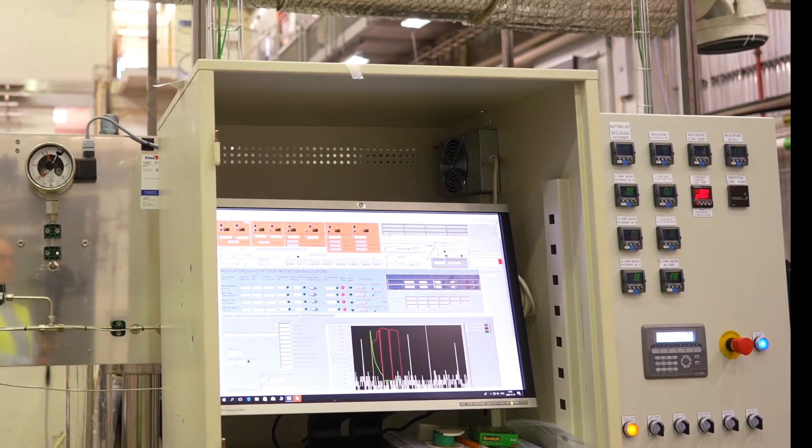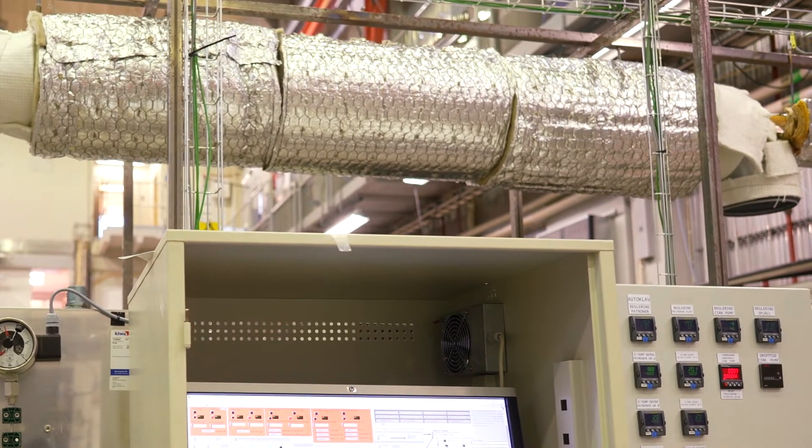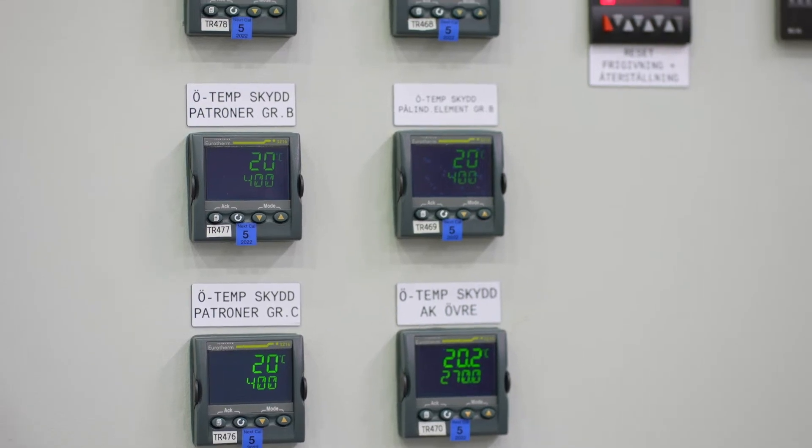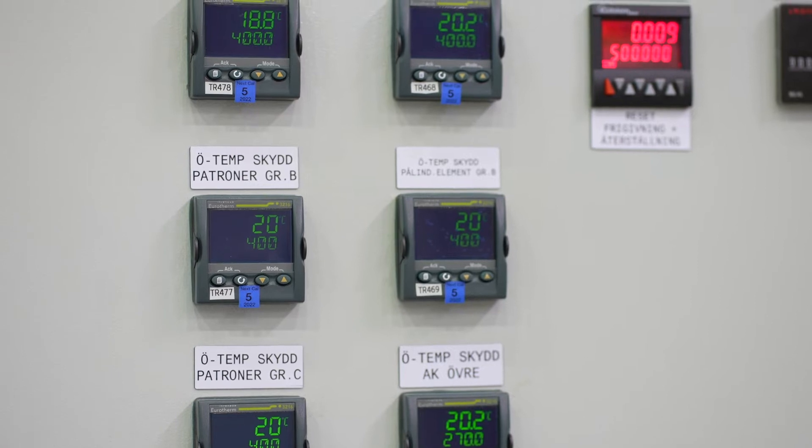There are two high velocity test loops specially designed to simulate the real flow conditions of nuclear reactors. Flow accelerated corrosion and other mechanisms that require a high flow velocity could be studied here.